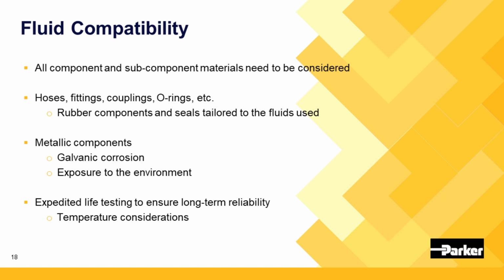Another key is fluid compatibility. All the components and subcomponents need to be considered for this. All the hoses, fittings, couplings, O-rings, everything needs to be set up to make sure that it's compatible with the particular fluids you have. If you've got an oil system, dielectric oil for immersion versus a glycol water system, you're going to be using different O-rings, different hoses, and you want to validate that those are compatible with the particular system that you're using. The rubber components are tailored to those particular fluids, and significant testing is typically done to make sure that they are compatible.